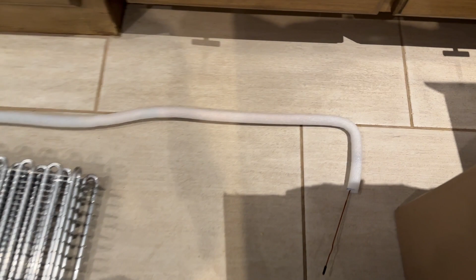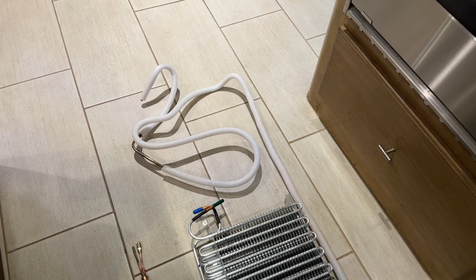The bottom part goes to the evaporator, which is right here, and the top part has a weird shape, but that shape actually wraps around the compressor and the top of the condenser coil. So I wouldn't change that shape much. When you put it in, you'll see which way you have to bend it a little to make it fit and work perfectly.